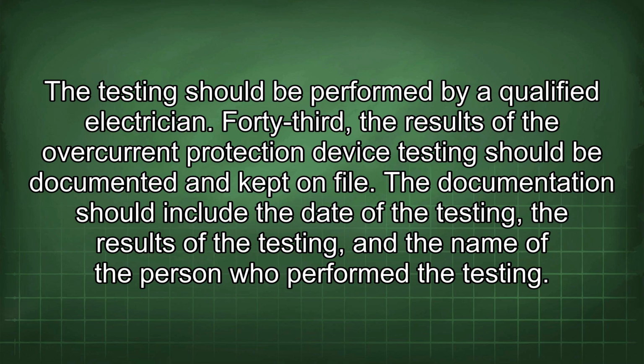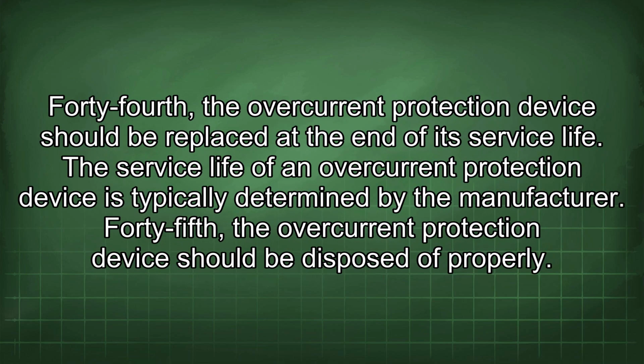43rd, the results of the overcurrent protection device testing should be documented and kept on file. The documentation should include the date of the testing, the results of the testing, and the name of the person who performed the testing. 44th, the overcurrent protection device should be replaced at the end of its service life. The service life of an overcurrent protection device is typically determined by the manufacturer.